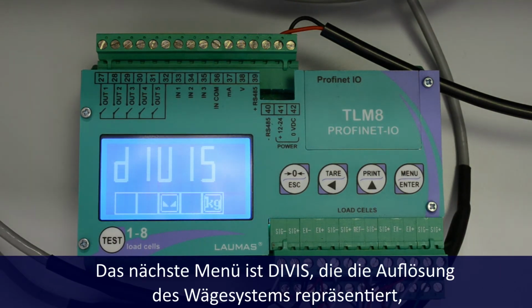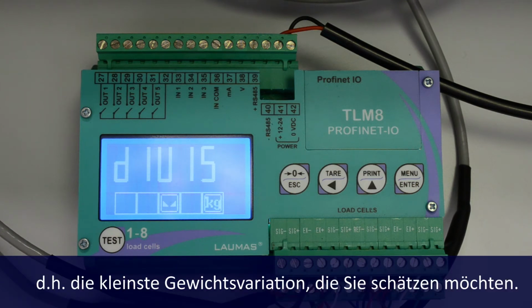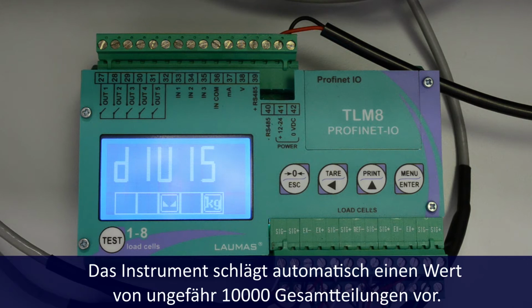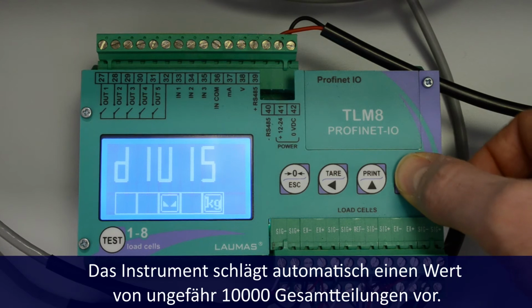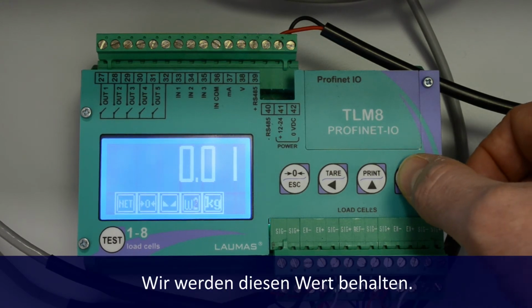Next is DIVIS, which is the system's resolution, the minimum weight variation you want to appreciate. The device automatically proposes a value which gives you around 10,000 total divisions. We will keep it.